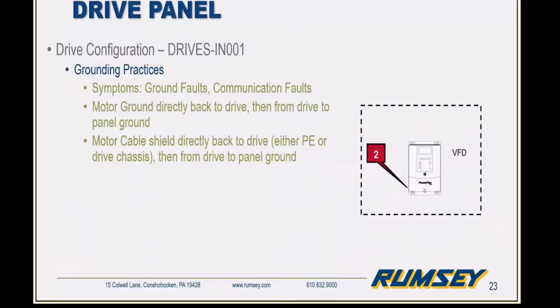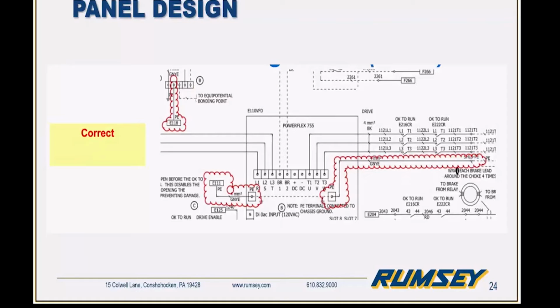Moving on to the drive panel, again, as noted earlier, grounding is important. There's no difference here in the panel. Improper grounding practices often result in nuisance issues, whether it be ground faults or communication issues. Many times the motor ground isn't tied in correctly. What we'd like to see is the motor ground coming back from the motor. The leads should go directly back to the drive and then to panel ground, and that goes the same for the shield as well. So the shield and the motor cable should go directly back to the drive before going on a separate cable to the panel ground.